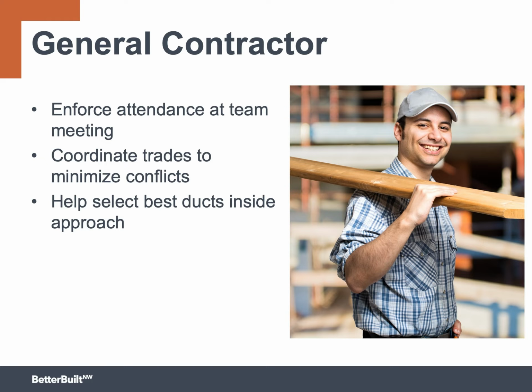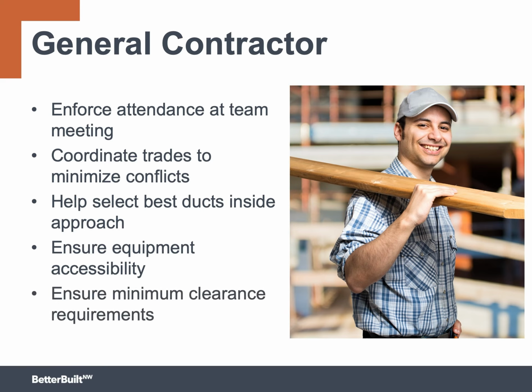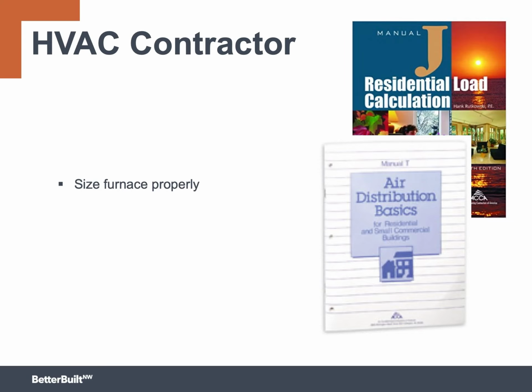Any indoor location for equipment will be much tighter than a garage or basement. She needs to make sure that the equipment will fit in the designated space and will be accessible for maintenance. And finally, she needs to ensure that any minimum clearances and fire codes and all technical requirements are met. The HVAC contractor plays the key role in this whole process, so they absolutely need to be involved with the design up front and attend the team meeting before construction starts.